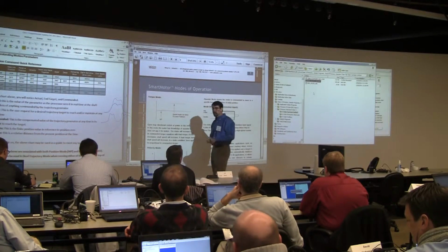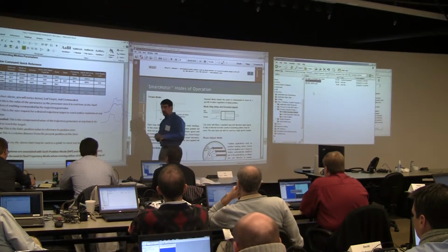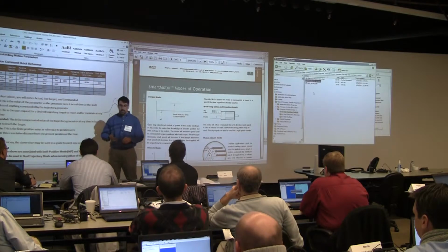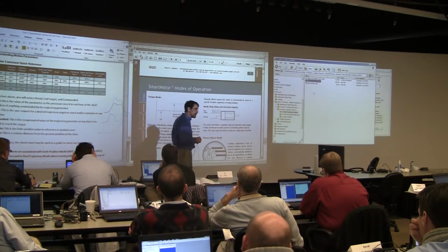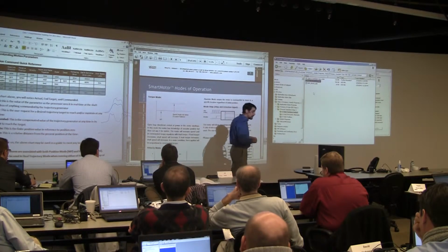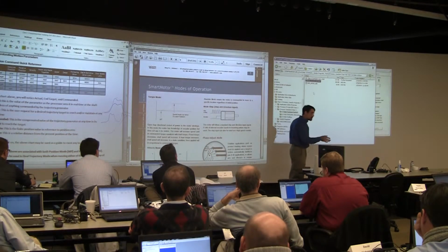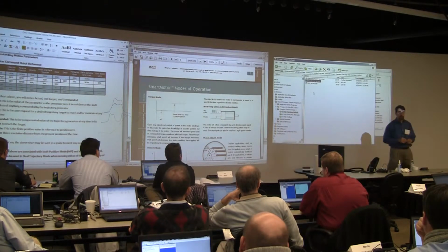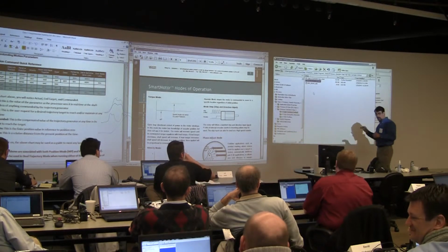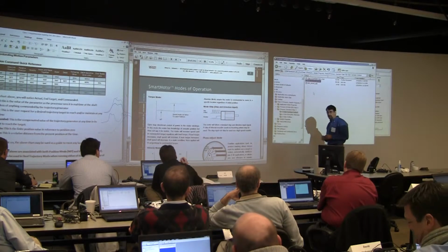If there's no firmware in this motor, you will not be able to communicate with it normally. You'll see flashing LEDs and a watchdog fault and all this other mess, and you won't be able to use it. No one in this room should ever see that happen. Well, I say no one. There's a few guys in here that work in production that might. But otherwise, no one should ever see that happen.